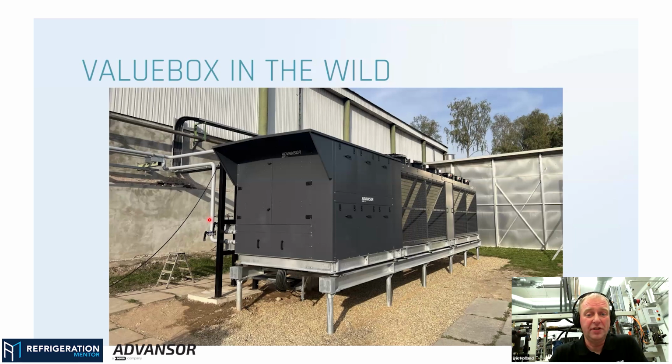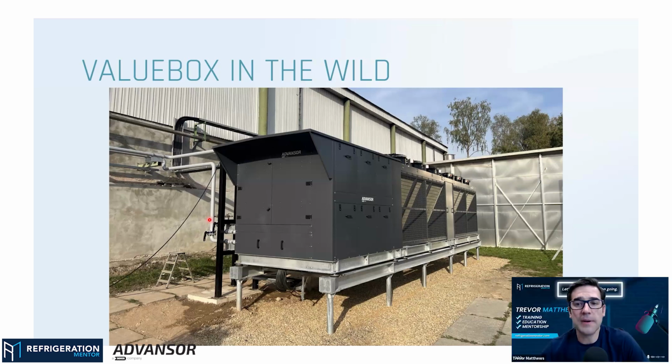And as more capacity is added, you also need to charge more CO2, because your evaporators will be more and more flooded. So it's a waiting game. You fill it up a bit, wait to see what happens, fill it up again, check some more, fill it up again, and you do this over the course of an hour or something. And this system here, from when we got power on it until we had a running system, with still some fine tuning of course, was about 2.5 hours. But that was after everything was checked and verified.